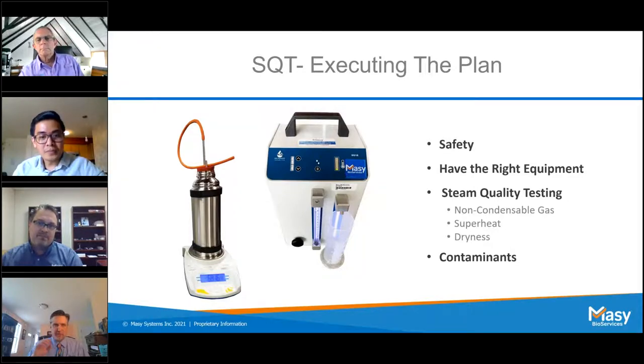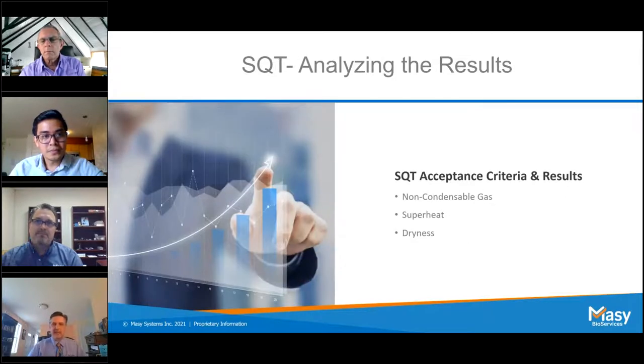Great. Thank you. We'll be talking in a minute or so a little bit more about the results and analyzing those. The last bullet point on here is on contaminants. If you look at EN285, there's Annex B and there's also Table 4. Within those, it does talk about contaminants, and it's talking about the feed water. It's also talking about the clean steam condensate being tested for many different things, whether it's lead or endotoxin. Those tables are within the EN285. They're also listed in HTM 01-01 and in that EN13060 document that I mentioned earlier as well. All right, so let's move on to analyzing the results.